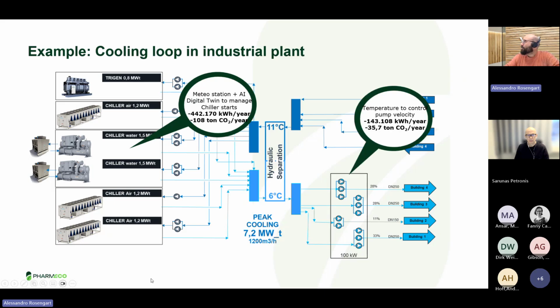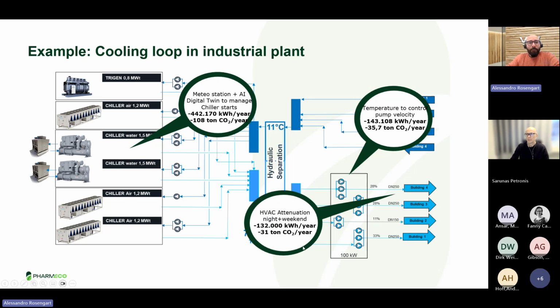Another thing we could improve was how the water was distributed on the secondary loop. The approach was to keep all the pumps at maximum speed always. This meant that when the need for water was less, there was simply a waste of energy from these pumps, which are 100 kilowatts of installed power, always working at maximum. There were some inverters, so we added a control system that allows us to reduce the speed of the pump following the need.